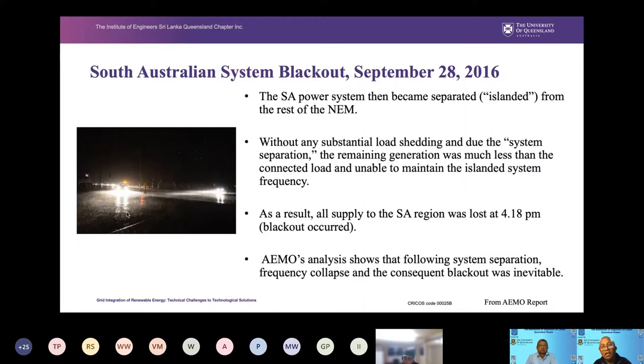And we will see shortly the ROCOF, the so-called rate of change of frequency. The drop was so significant that none of these protection schemes worked, and then everything tripped. So without substantial load shedding, the system separation was imminent. And then at about 4:18, the blackout happened. So the AEMO analysis showed the frequency collapse was inevitable.